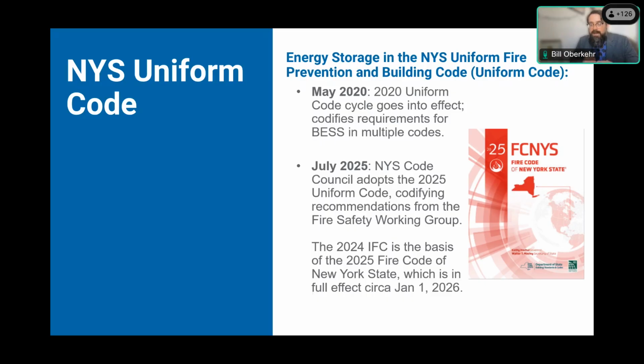If you took our section 1207 right now and put it side by side with the 2023 NFPA 855, you'd see that New York is exceeding those national standards. We are, to my knowledge, the first state to do that, beyond New York City. The national standards-making bodies have actually started to look at what New York has done and incorporate that into their standards, creating a feedback loop of influencing each other to make these systems as safe as humanly possible without over-regulating to the point where we destroy the industry. That's the needle that needs to be threaded with this type of regulation.